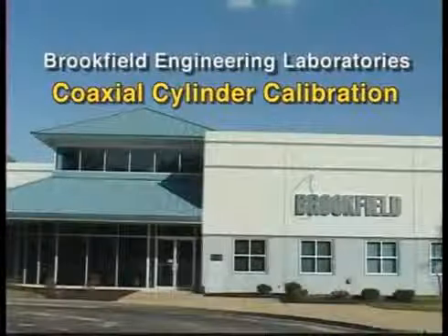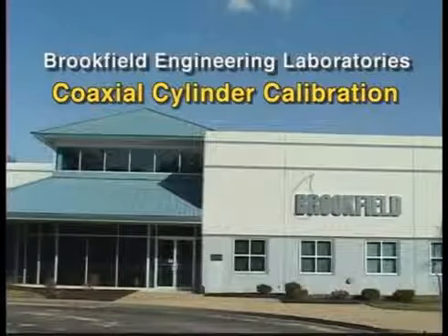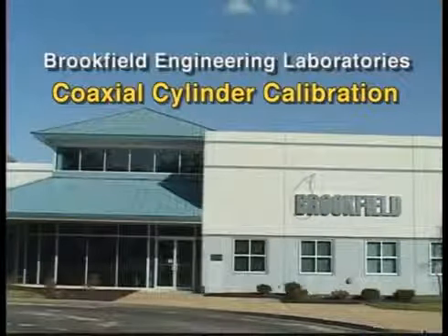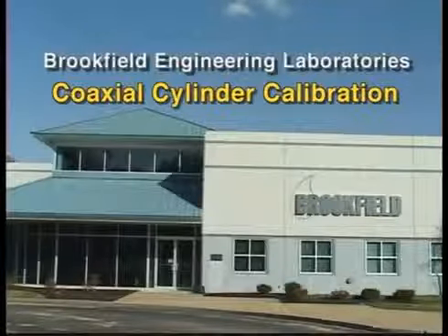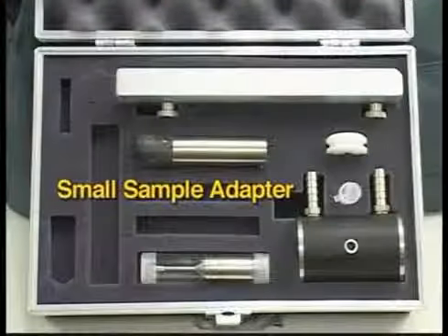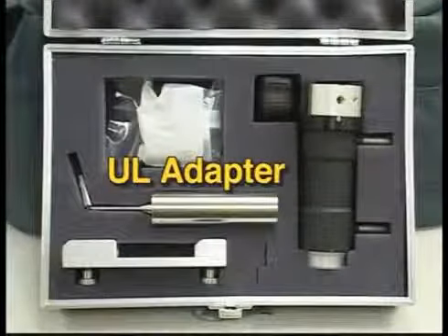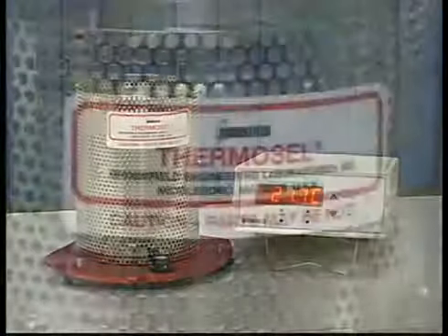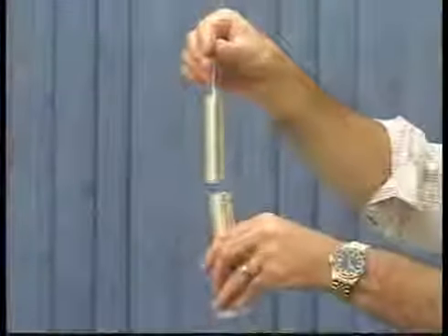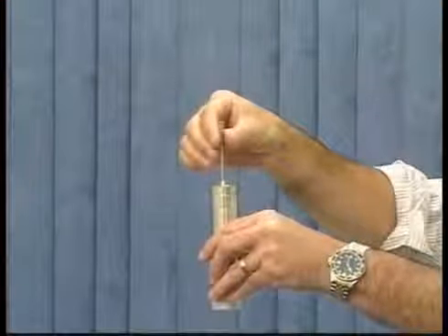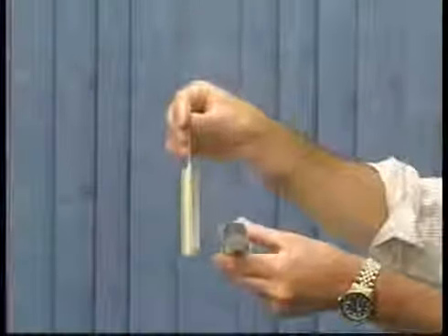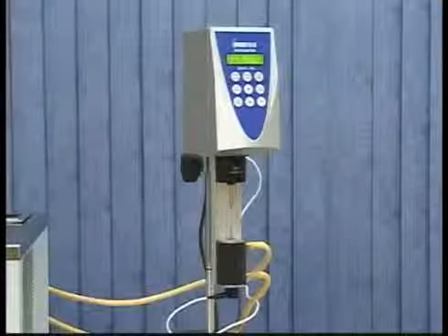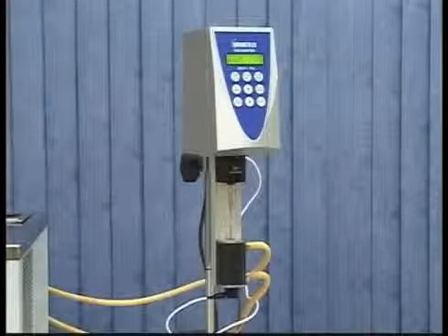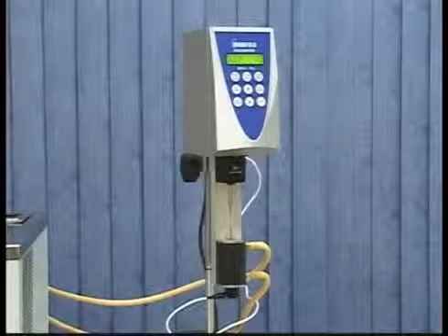This video will show the calibration routine recommended by Brookfield Engineering for our coaxial cylinder geometry accessories. These accessories consist of our small sample adapter, enhanced ultra-low viscosity adapter, thermocell, and DIN adapter. These adapters are all based on defined coaxial cylinder geometry. To ensure your viscometer is working properly when using these adapters, a periodic calibration check is essential.